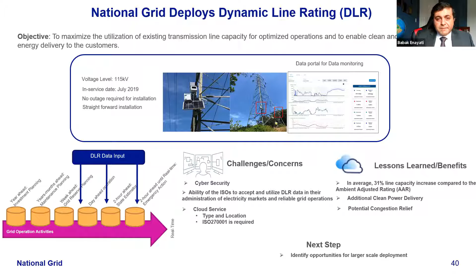Let's get to some field data. This is sample information comparing DLR with ambient adjusted rating and static rating from March of last year until July of this year. The data shows DLR exceeds static rating 94 to 97% of the time, though at times the blue line does dip below the red.